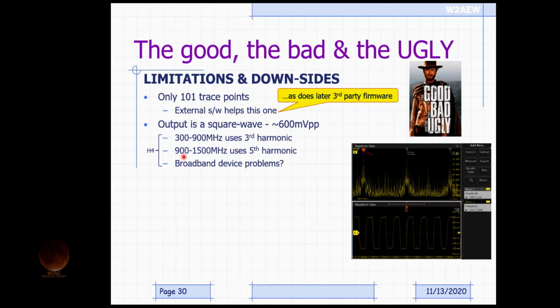And from 900 meg to 1.5 gig, it uses the fifth harmonic of the square wave. Okay. So this output that I'm showing you right here is a 200 megahertz square wave. It's the same exact signal that's used to measure at 600 meg and at 1 gig, right? Because that's the third harmonic and the fifth harmonic of that square wave. So it's not a pure RF signal generator, okay? It's a square wave generator that's got all this harmonic energy. So you have got to consider whether the device you're measuring is going to have a problem with that, okay?